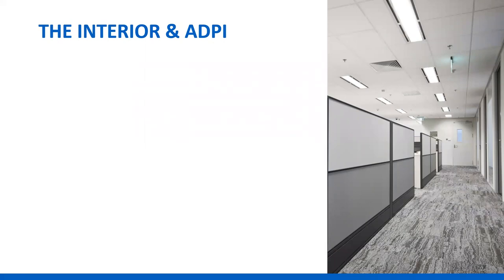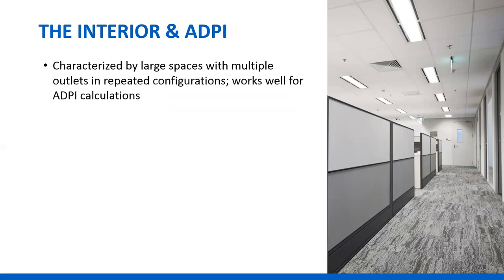Another thing different about the interior zone: it's typically characterized by multiple diffusers in repeated configurations that lend themselves to the use of the Air Diffusion Performance Index, or ADPI. ADPI can be measured in a laboratory and used to predict air motion and uniformity of temperatures within a space. We spent a lot of time talking about that in the last session.